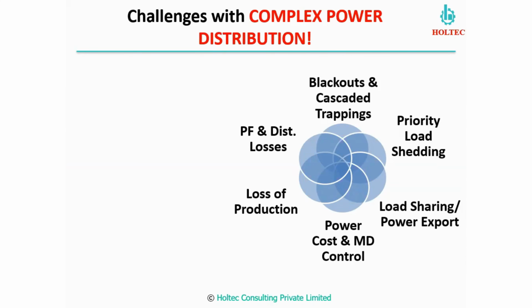Now, we have multiple lines, maybe 3 lines, maybe 4 lines. In some cases, 4 lines are running, right? We have different sections in the plant lines, so we have multiple loads available for load shedding. Now there is a requirement for prioritization of those loads. For example, at this moment the least priority load may be the cement mill for line number 1. But maybe after a day, or next day, or maybe after 8 hours, there will be a huge demand for cement, and then cement mill operation will become very critical. So the priority will shift to, say, the raw mill for line number 2.